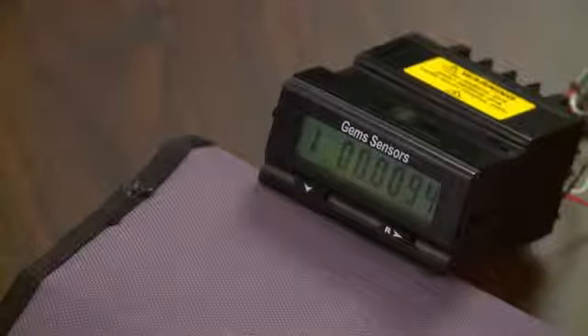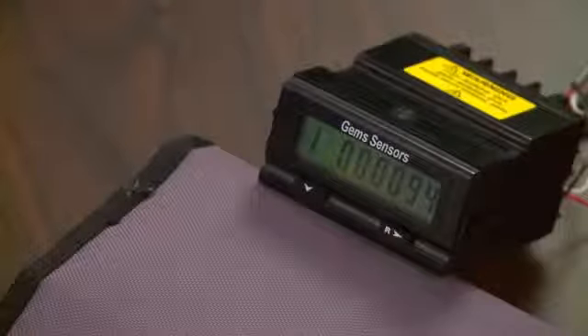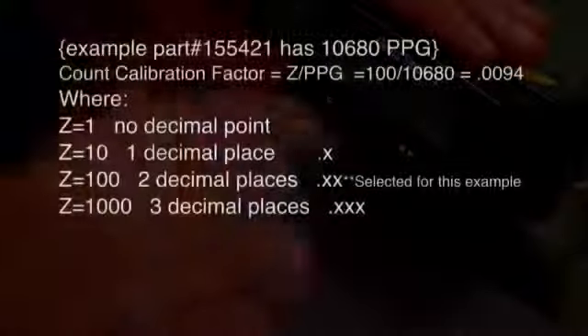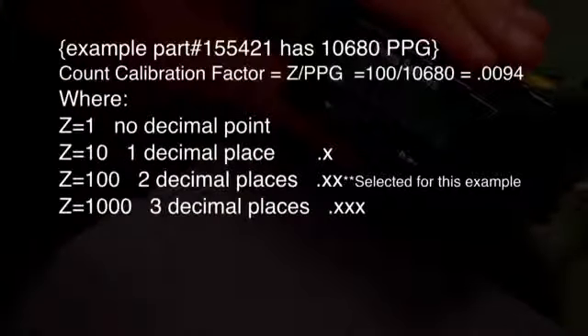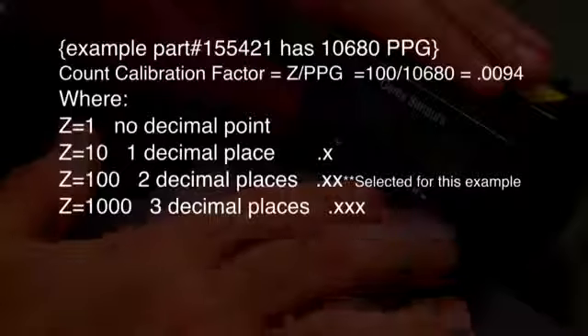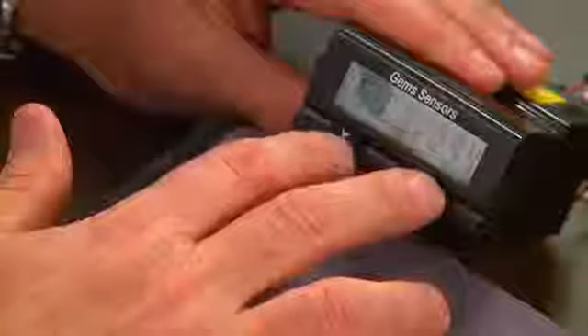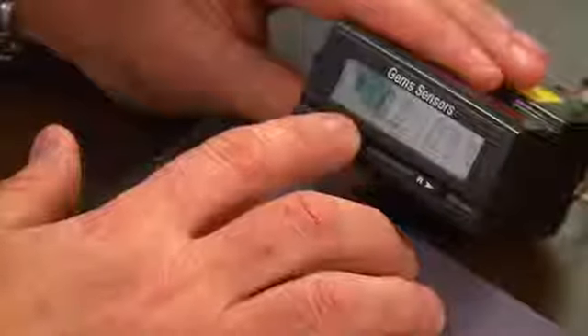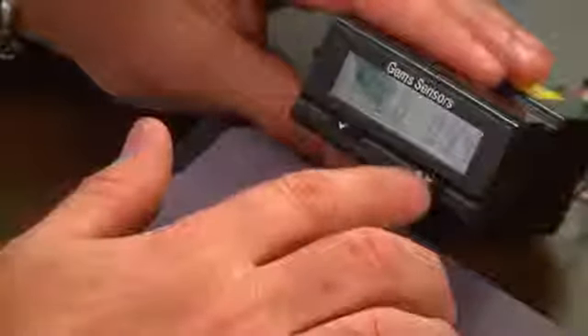We're at step 1. This is where we're actually going to enter in the calibration factor for your total gallons a minute. As we can see, the number that's been placed in here is 0.0094. The math will be shown to you separately. And again, it's only derived by knowing the number of pulses that equal 1 gallon. How you actually change the number, you'll use this key on the far right to light up the point or the digit that you want to change. You then use the other key to scroll down to it. I'm going to leave the number that I have in there. The math has already been done. It's 0.0094. You scroll to the end. When you're ready to move on to step 2, you press your down arrow, you go to step 2.